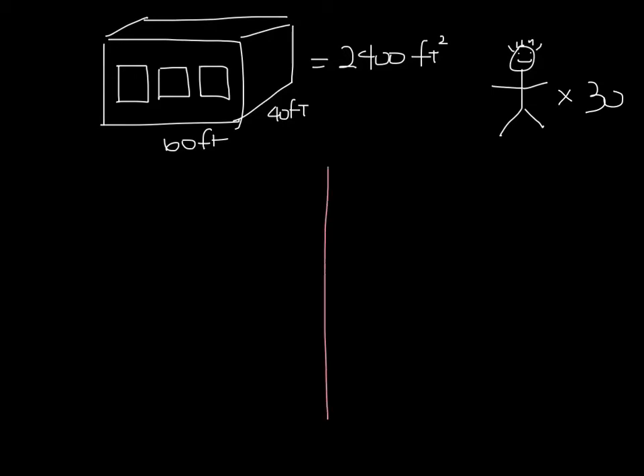Now let's compare how much airflow you would need for a traditional system versus a chilled beam system. If you had a traditional VAV system, you'd have about 1 CFM per square foot, so you'd have 2,400 CFM in this building.